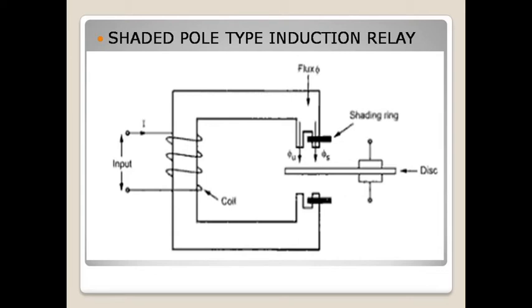Due to this phase difference of two fluxes, it generates a rotating magnetic field. This rotating magnetic field induces an EMF in the aluminum disc, and as EMF is induced, eddy current flows in the disc.